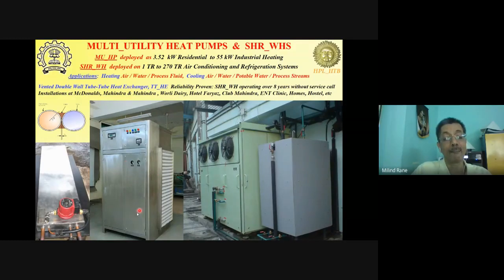So this is an example of a 3-in-1 heat pump which was deployed in the industry, namely Mahindra and Mahindra. And then we have here another example where we have a multi-utility heat pump which is directly connected to the indoor coil of the McDonald's kitchen. So that is a DX cooling provided for a 24-ton capacity in the kitchen area. And this also co-produces hot water for dishwashing and cleaning and other sanitation purposes.